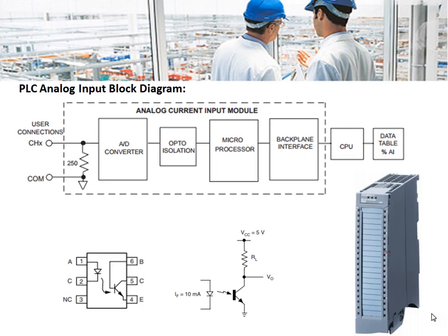The voltage is then fed to an ADC — analog to digital converter. The common types of ADCs used in PLCs are successive approximation type and Delta-Sigma type. After digital conversion, the signal is opto-isolated and fed to a microprocessor or microcontroller, and through a backplane interface it is fed to the CPU of the PLC.